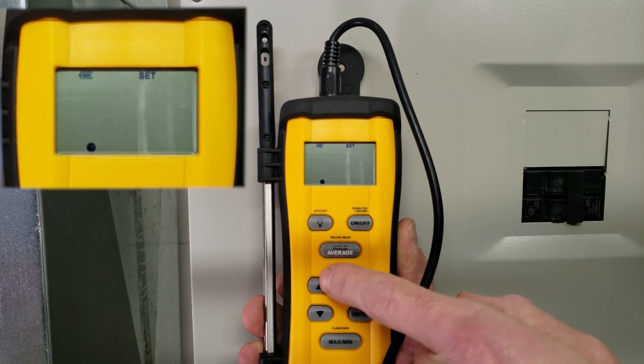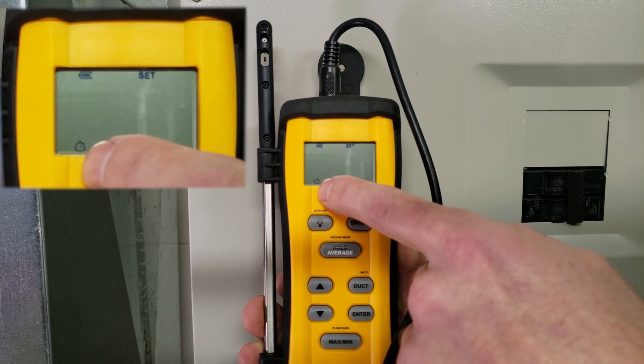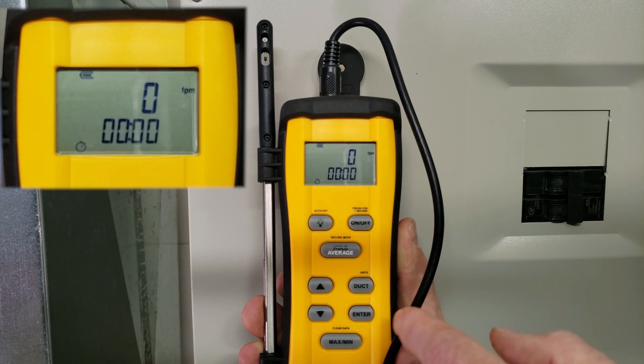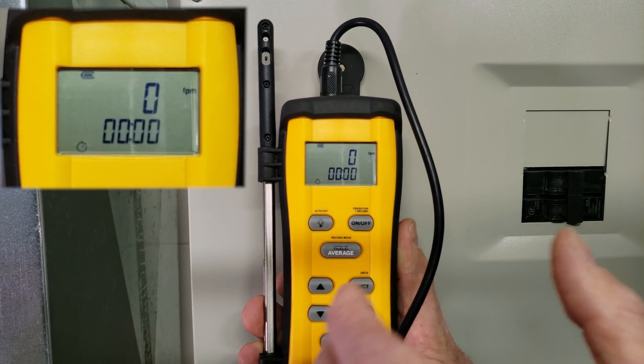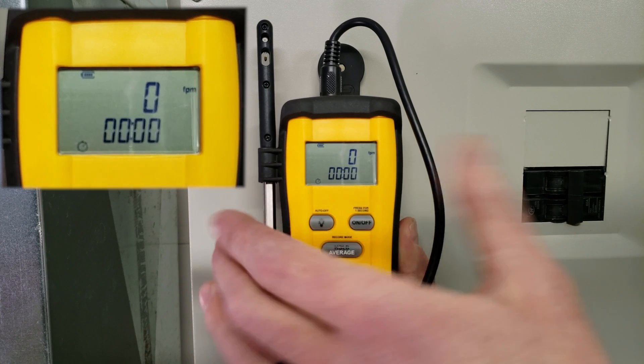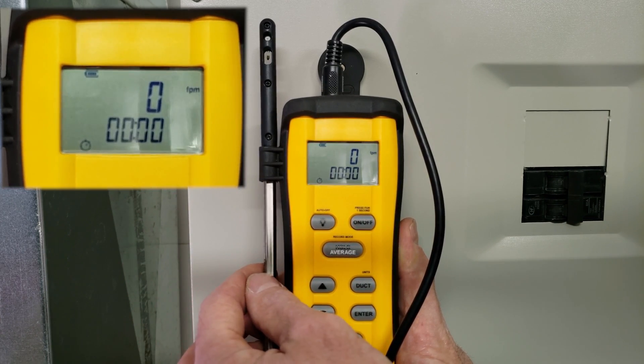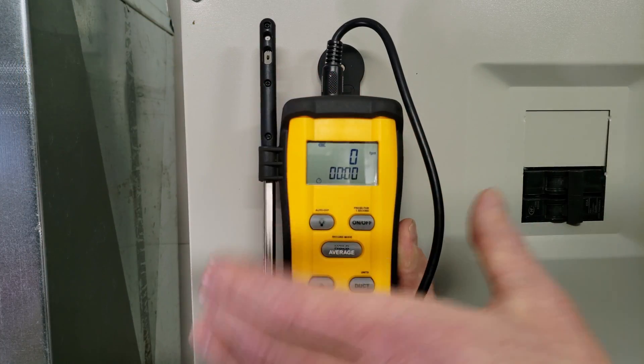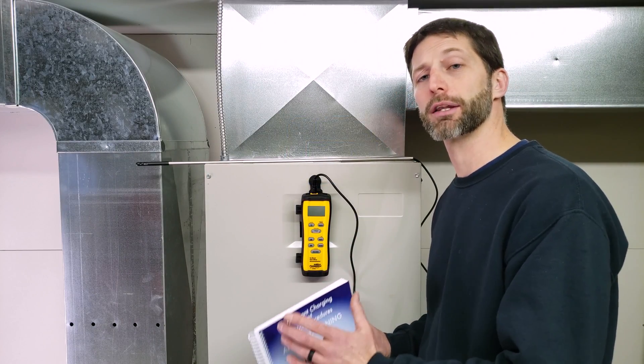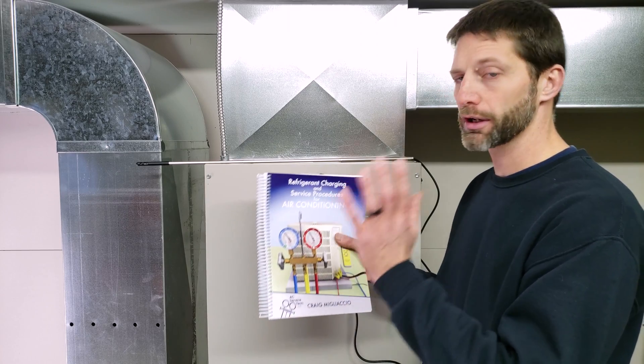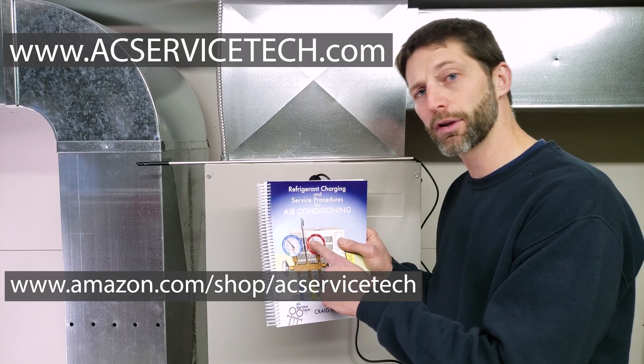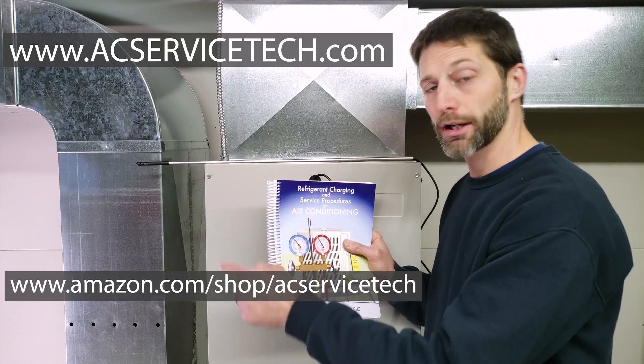We have our clock ready. When we get the probe all the way in the duct, we press enter to start timing. We're putting the probe at different depths inside the duct in five different holes to get an average CFM for the whole duct. It's very important to check airflow in preparation for checking refrigerant charge. Check out our book available on our website and Amazon.